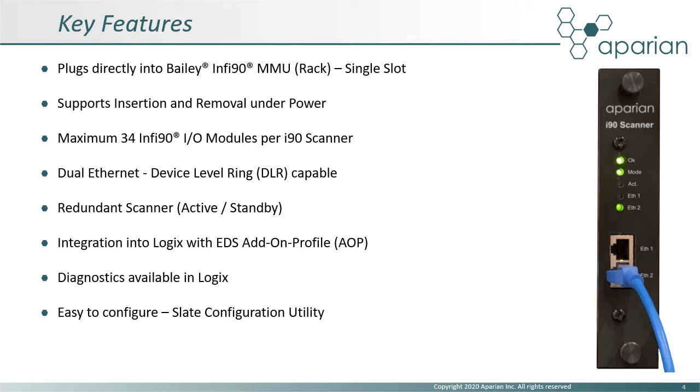A pair of i90 scanners can be configured in a redundant, active-standby configuration. Integration into Logix makes use of an EDS add-on profile, which provides IO module data and diagnostics in an intuitive tag structure. Configuration of the scanner and IO modules makes use of the Aparian Slate configuration software.